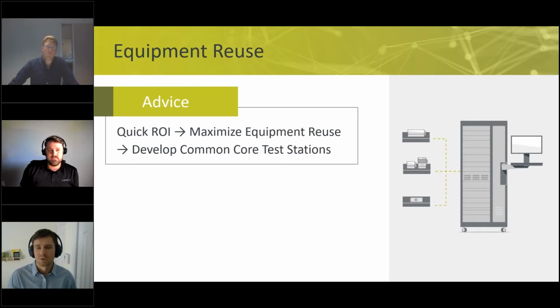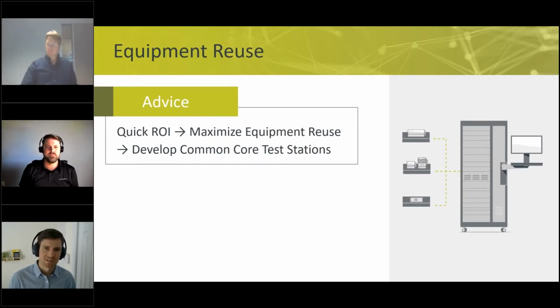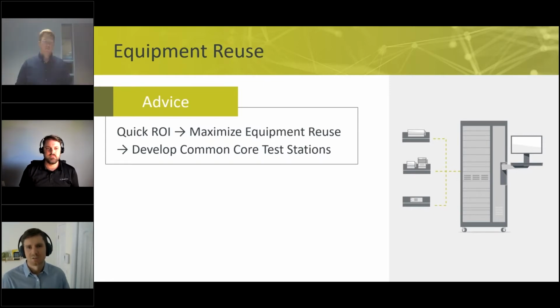Of course. So when considering the design of a common core or generic station, the main and most important question to ask is, how do I maximize instrument usage? Test equipment can get expensive, and it is particularly costly when it is underused, like in the case you described, Alex. You must make sure the test station can share tasks among different product types, but doesn't have more equipment than necessary. You can do this by building an unchanging station core with the ability to swap unique fixtures in and out to accommodate different products.